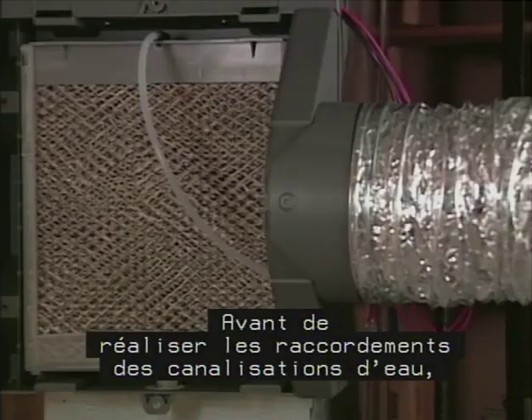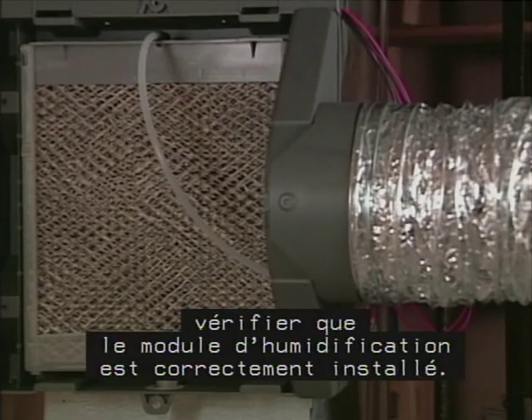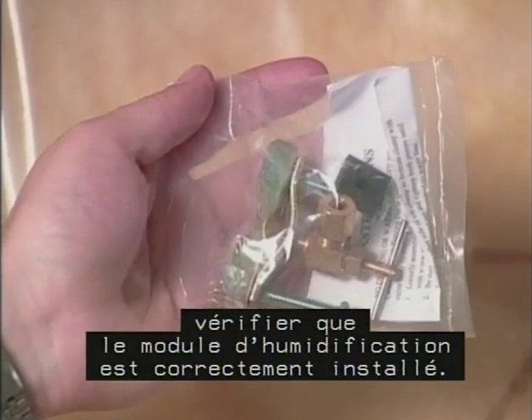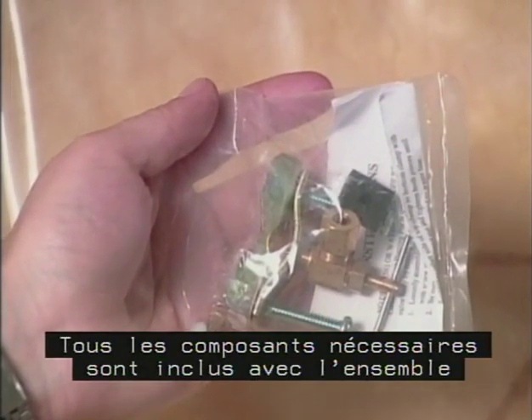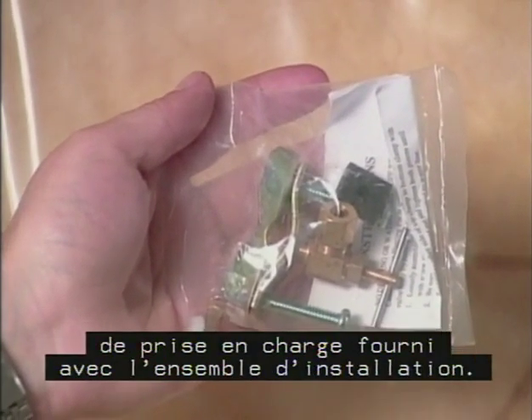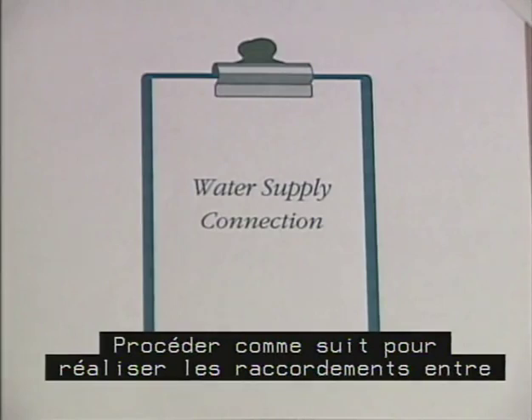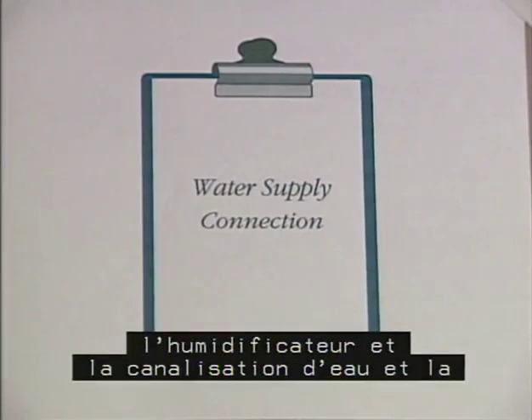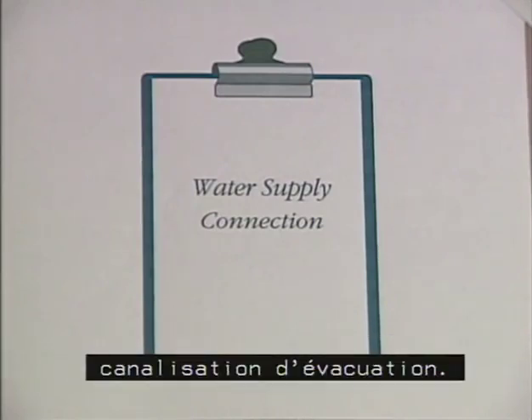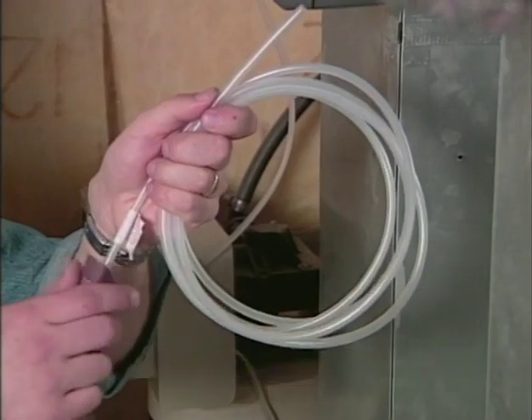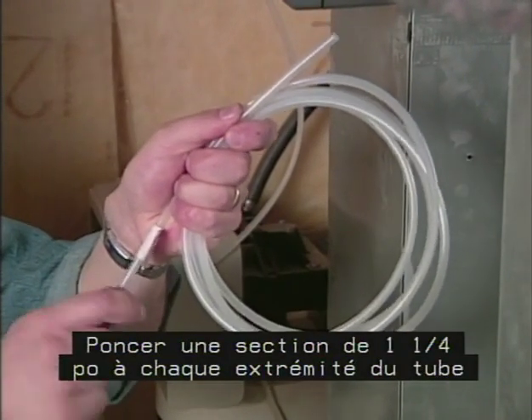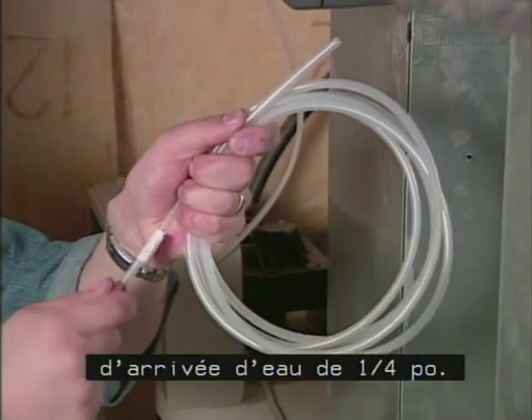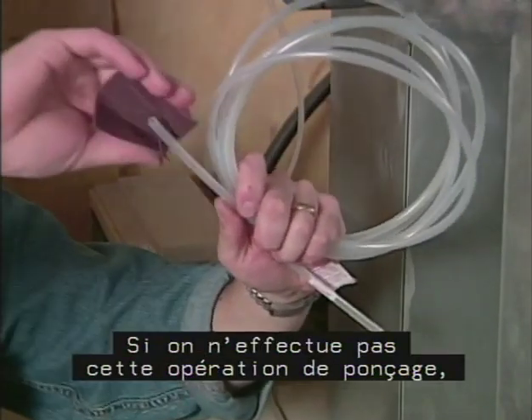Make sure the evaporator pad is installed correctly before making the water connections. All required hardware is supplied in the saddle valve kit in the installation package. Do the following to make the water connection to the humidifier, the valve connection to your water supply, and the required drain connection. Sand 1 1/4 inches of both ends of the 1/4 inch water supply tube. Failure to do so may result in leaks.